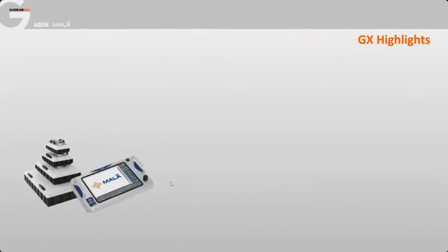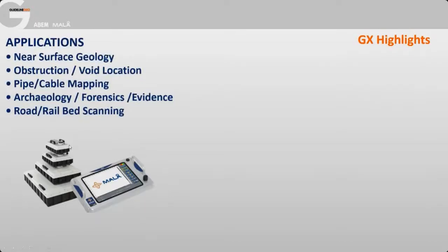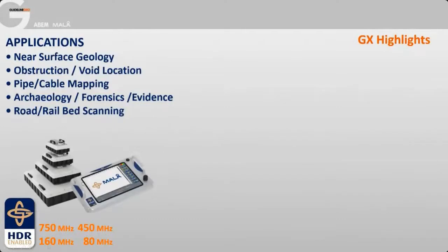The GX is our Ground Explorer. This instrument has slightly lower frequency antennas and is used for a range of work from engineering to archaeology to road and rail scanning, and pipe and cable mapping. It's basically a suits-all type of instrument, with antenna frequencies from 80 megahertz at the lowest up to 750 at the higher end, so a good mix of deep penetration and high detail. This system also has what we call HDR technology, which is high dynamic range. I'm going to briefly explain what that means.